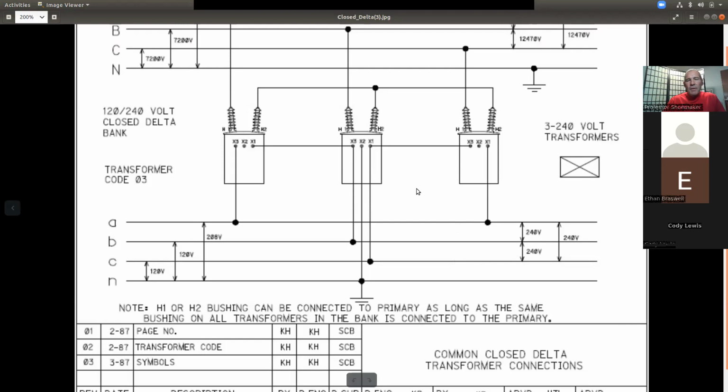It's an attribute of electricity that load imbalance, the imbalance of load between one leg and another, always follows the neutral. So load imbalance will try to go and find another path or an exit path on the neutral. But we really don't want that to happen. And that's why we float the neutral.